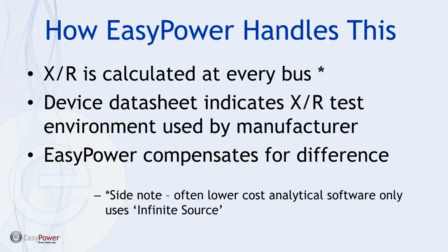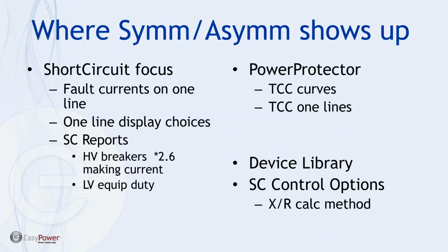All right, so then let's jump into where EasyPower actually uses this. We develop the parameters of symmetrical and asymmetrical current in short circuit, and we can show it both on the one line and in the reports. And then when we're doing a coordination in plotting the TCC curves and the one lines, this information is available and can be controlled as far as some of the application in the device library, and the way that the X over R calculations are being made themselves.